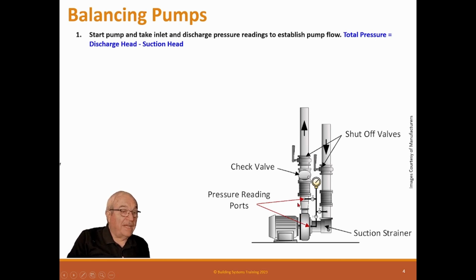You basically cannot use a pump for flow. I mean, to read flow for a pump, you can't use a pressure differential. So those have to be installed correctly. And if they are installed incorrectly, you need to make a big fuss and make sure the contractor changes those, because they're not only no good for you, they're no good for the owner later on. So they need to be changed. And by the way, we see them wrong all the time.